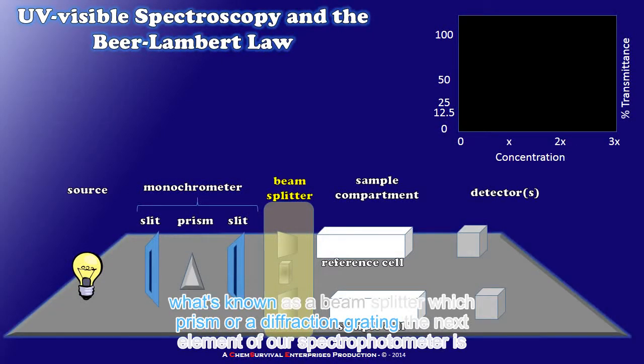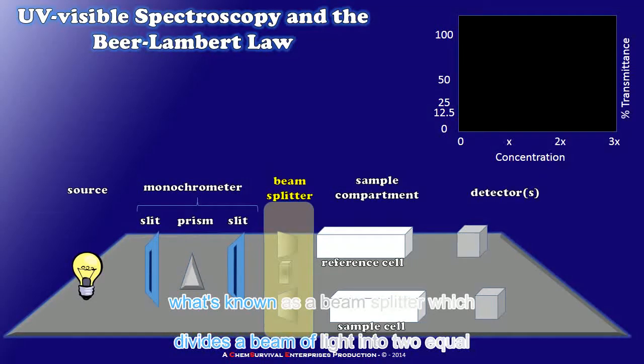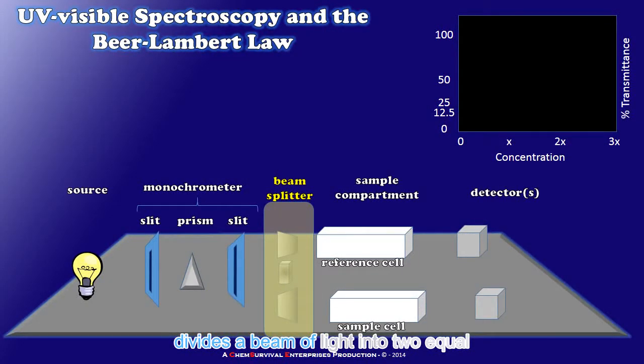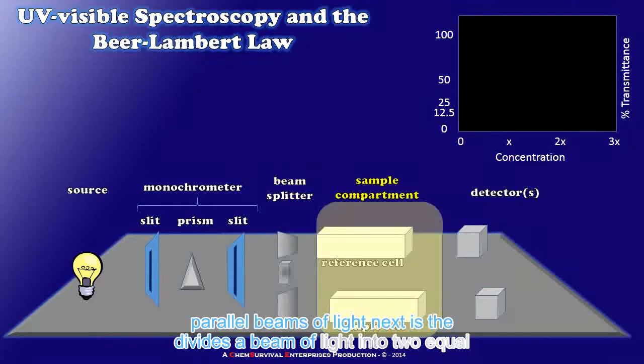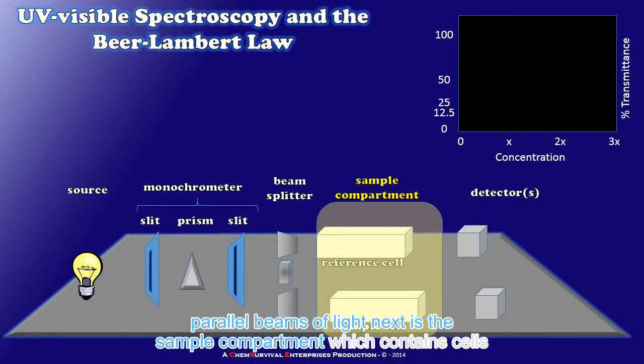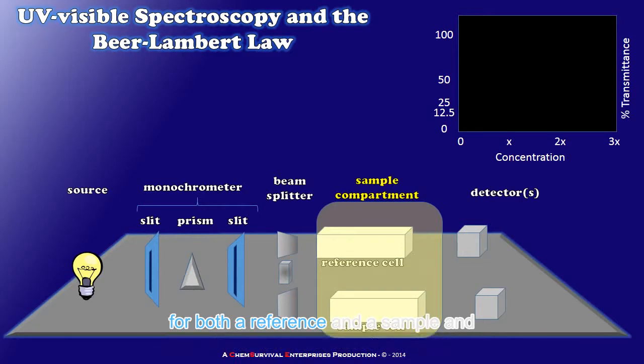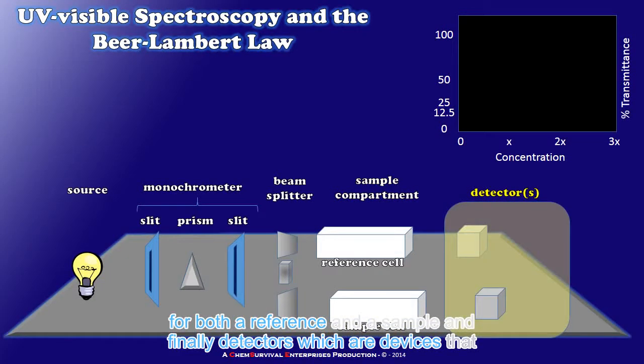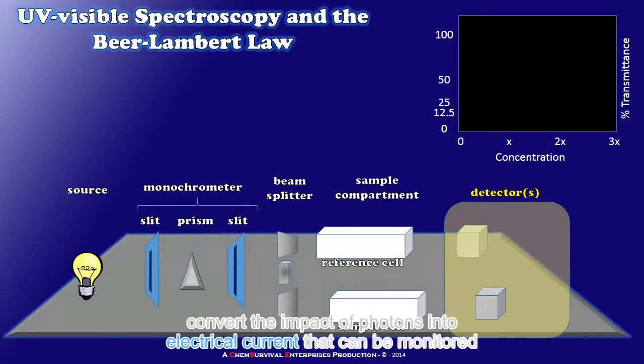The next element of our spectrophotometer is what's known as a beam splitter which divides a beam of light into two equal parallel beams of light. Next is the sample compartment which contains cells for both a reference and a sample. And finally detectors which are devices that convert the impact of photons into electrical current that can be monitored by a computer.